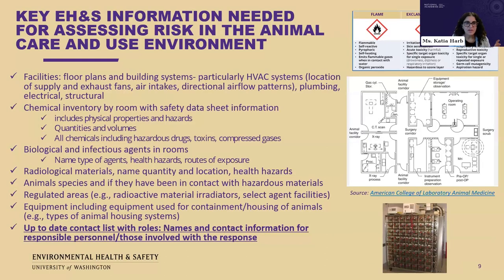Also with radiological and biological materials, if there are any highly secured areas to take into account, it's important to have information about the equipment used, the type of animal caging and housing. For example, if there's a ventilated cage rack, are there HEPA filters on the lids? If the HVAC fails, what is the potential for an infectious agent or hazardous material to escape a cage? Will it fail into a neutral airflow pattern? Those are all considerations for EH&S professionals in assessing risk and response.